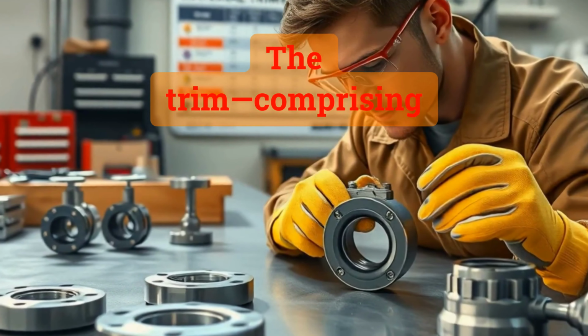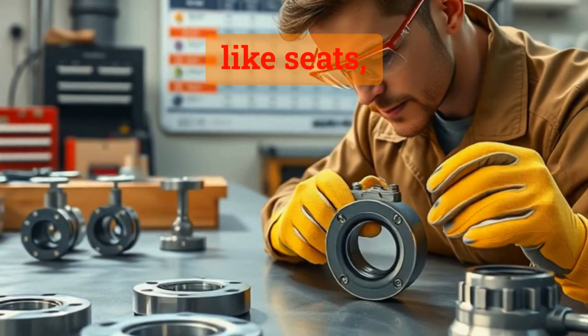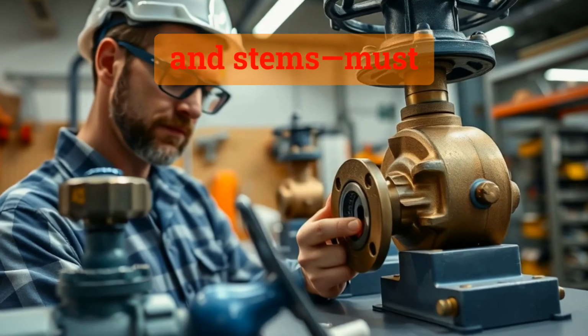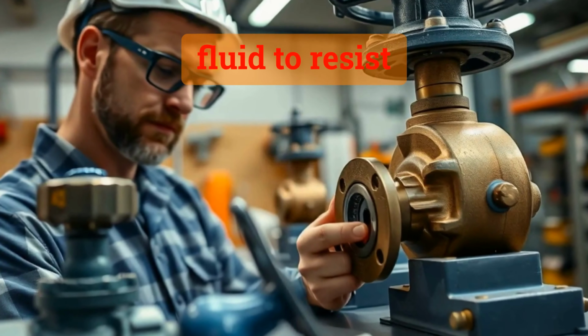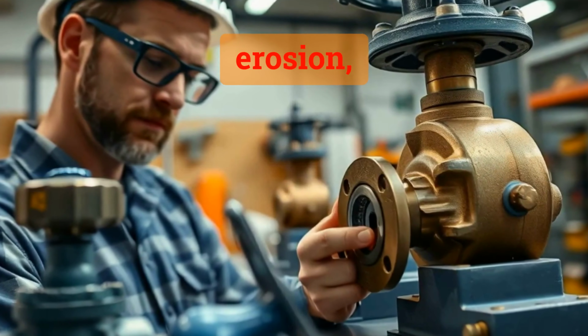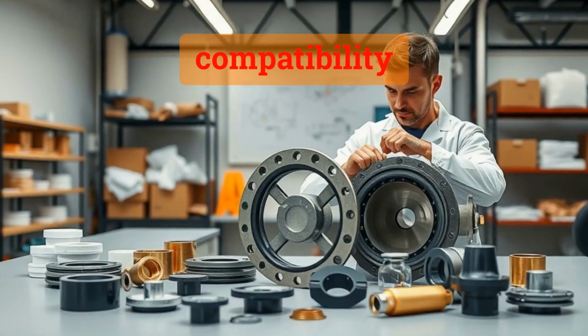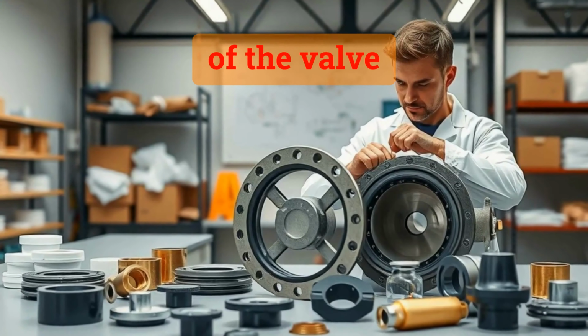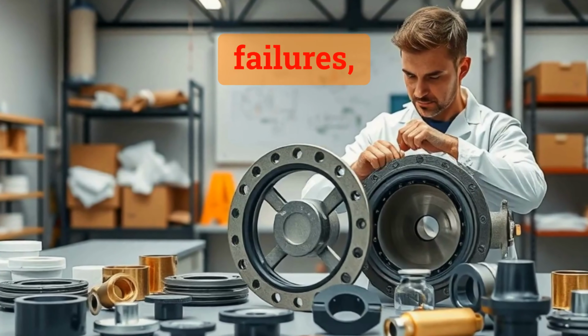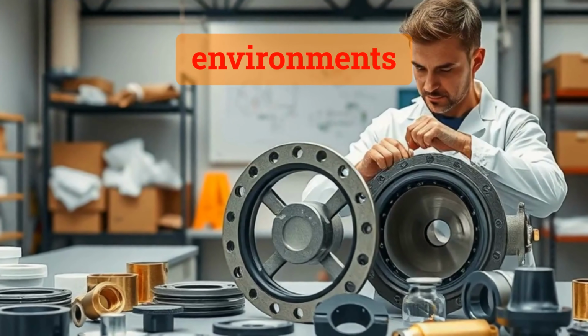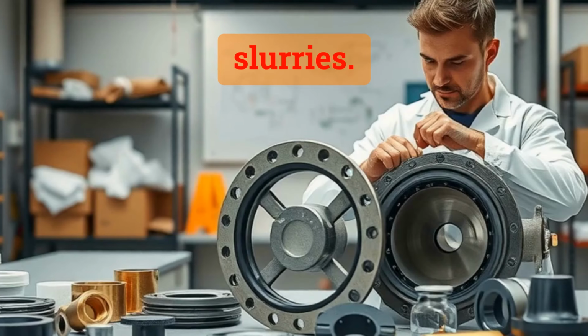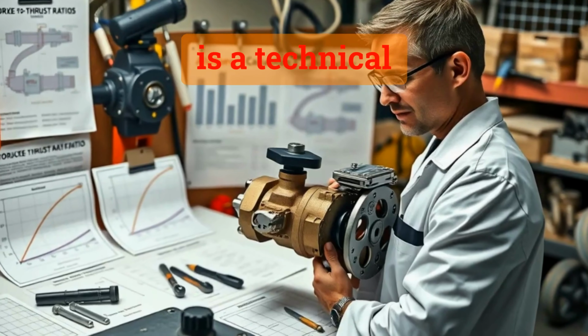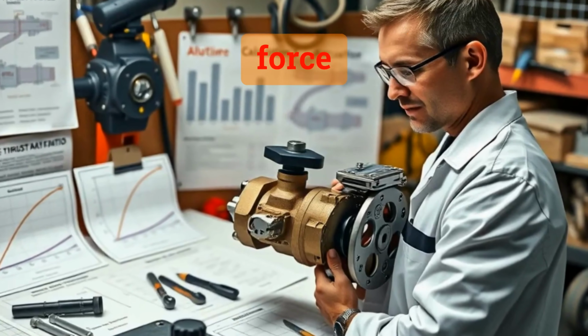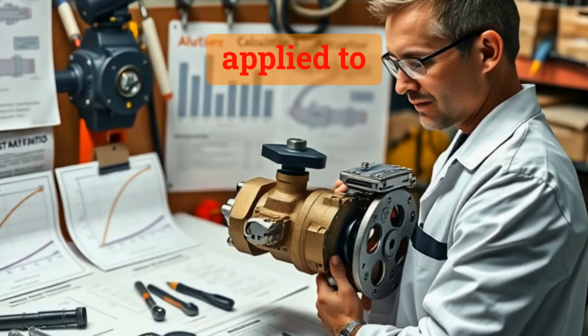The trim, comprising internal components like seats, discs, and stems, must be compatible with the process fluid to resist corrosion, erosion, and wear. Ensuring compatibility extends the service life of the valve and prevents costly failures, especially in challenging environments like acidic slurries.